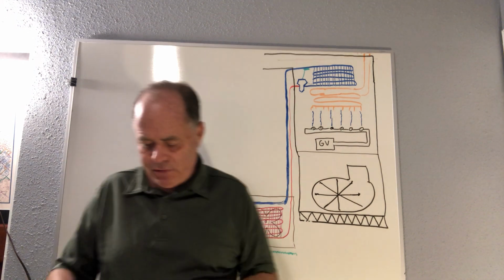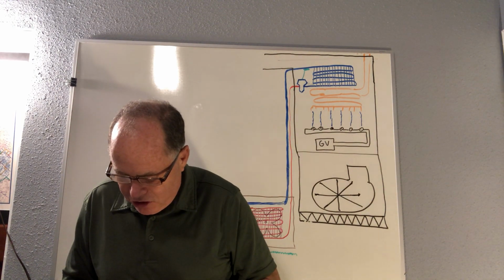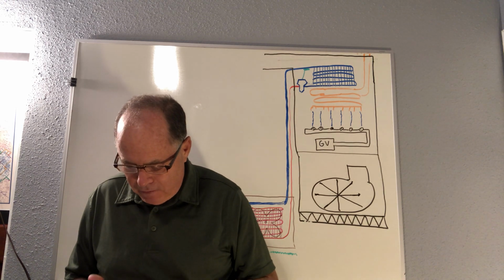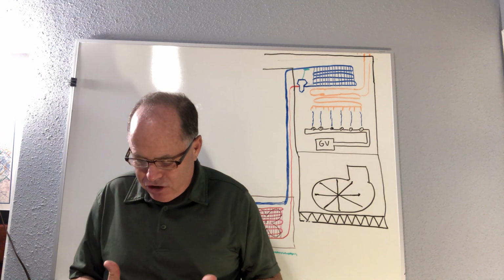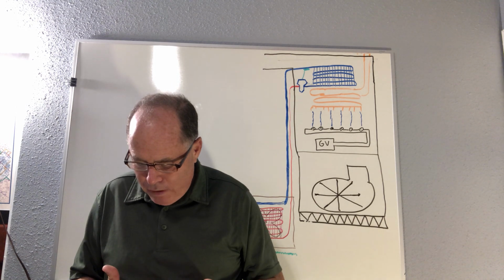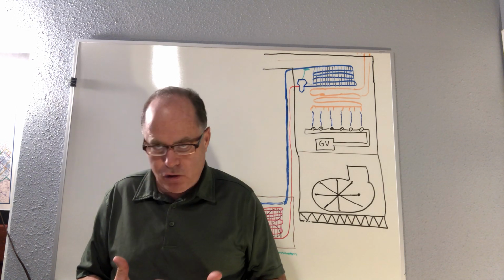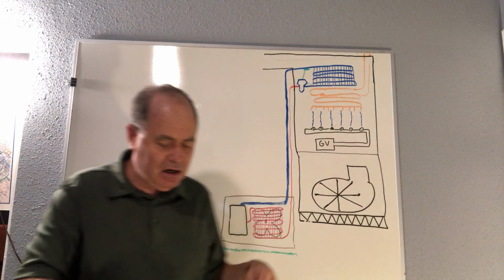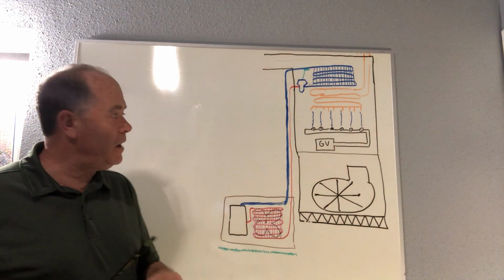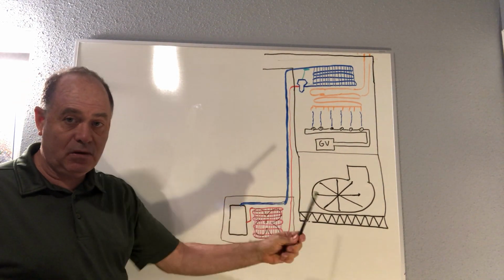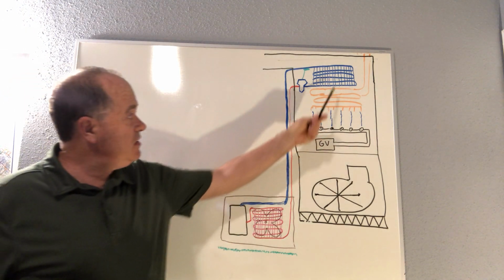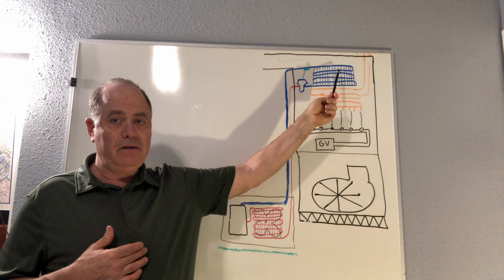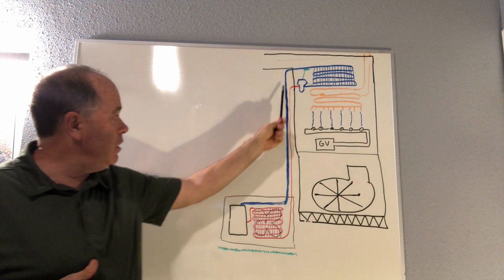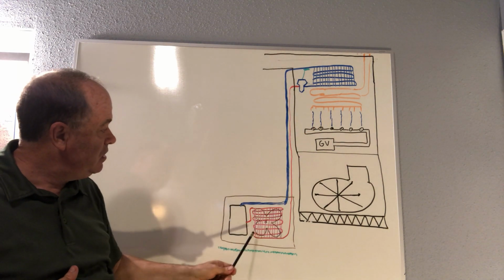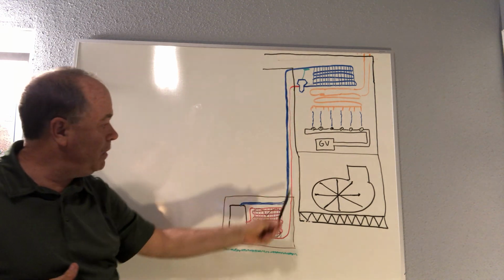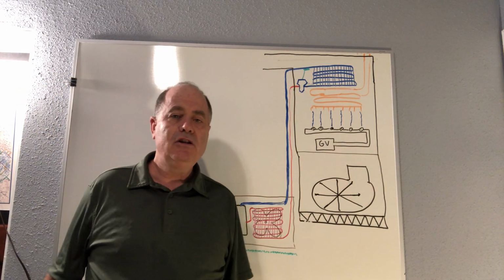That's why the next code was written that says furnaces shall not be located upstream from refrigeration coils unless the refrigeration coil is designed or equipped so as not to develop excessive temperature or pressure, which is the case here.